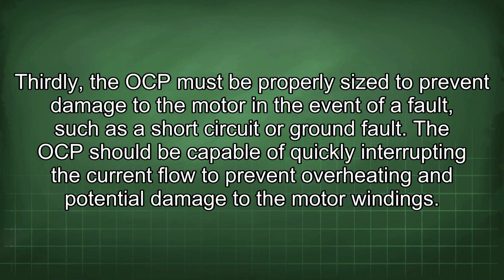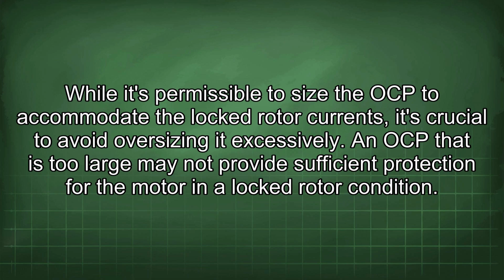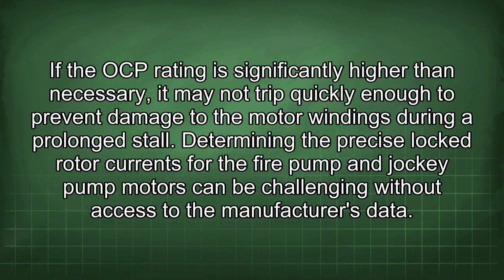Thirdly, the OCP must be properly sized to prevent damage to the motor in the event of a fault, such as a short circuit or ground fault. The OCP should be capable of quickly interrupting the current flow to prevent overheating and potential damage to the motor windings. While it's permissible to size the OCP to accommodate the locked rotor currents, it's crucial to avoid oversizing it excessively. An OCP that is too large may not provide sufficient protection for the motor in a locked rotor condition. If the OCP rating is significantly higher than necessary, it may not trip quickly enough to prevent damage to the motor windings during a prolonged stall.